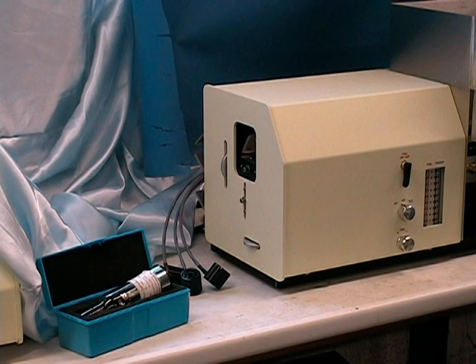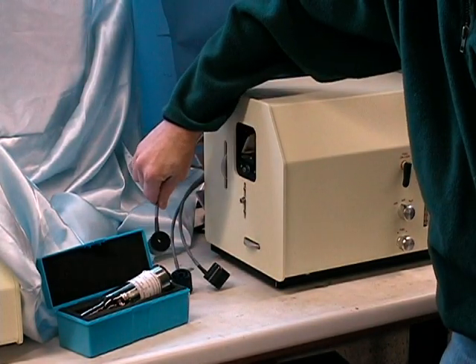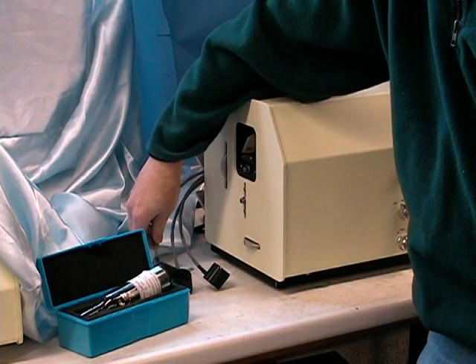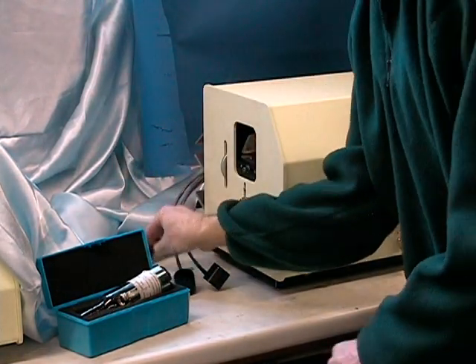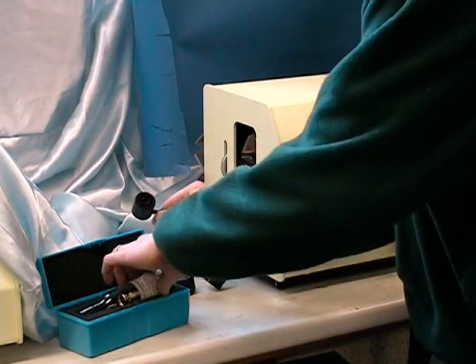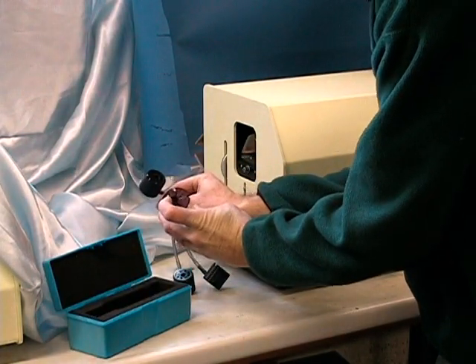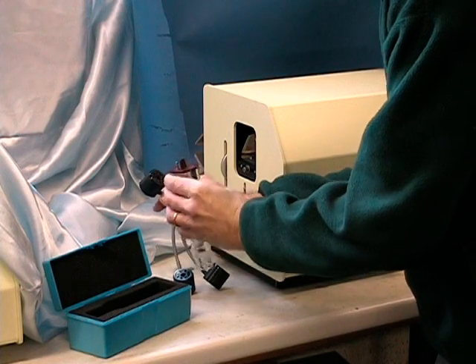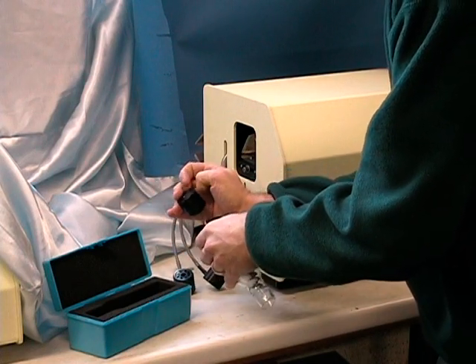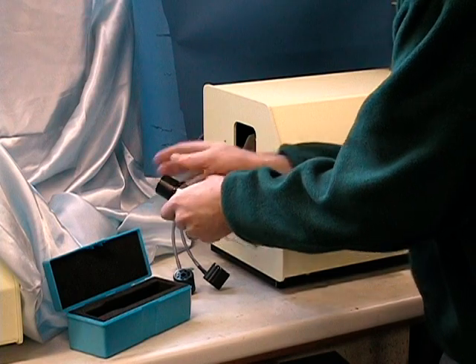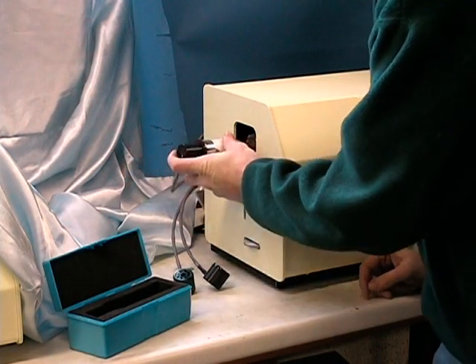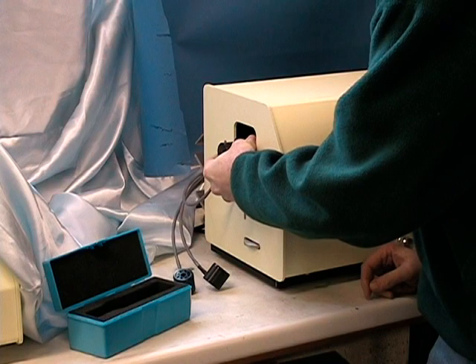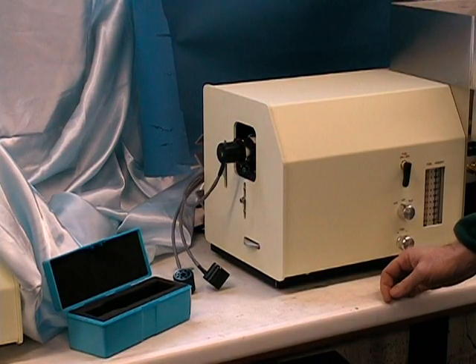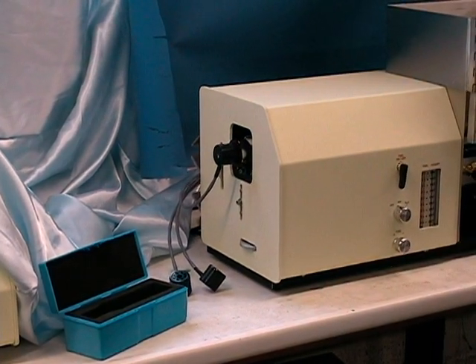The Buck 205 AA system comes with 3 lamp power supplies labeled on the ends 1, 2, and 3. The socket has a keyhole to match the key in the end of the 1.5-inch hollow cathode lamp. Again, be sure you have the right lamp socket based on the elemental file you've loaded. Insert the hollow cathode lamp into the spring-loaded clip on the left side of the instrument. At this point, we are ready to go to our alignment screen.